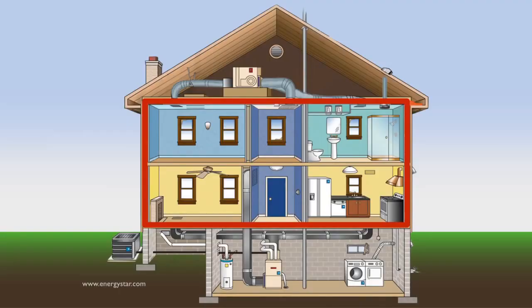Duct leakage is often the single biggest waste of energy in a home. Duct leakage testing is used to quantify the amount of leakage in a home's duct system. Because conditioned air can leak out or unconditioned air can be pulled in, it is important that these holes be sealed in order to save homeowners money and reduce pollutants from entering the home.